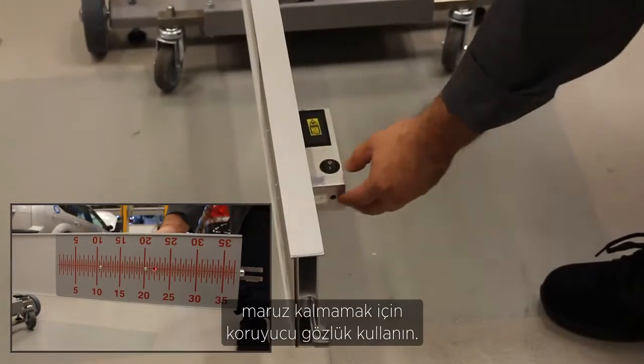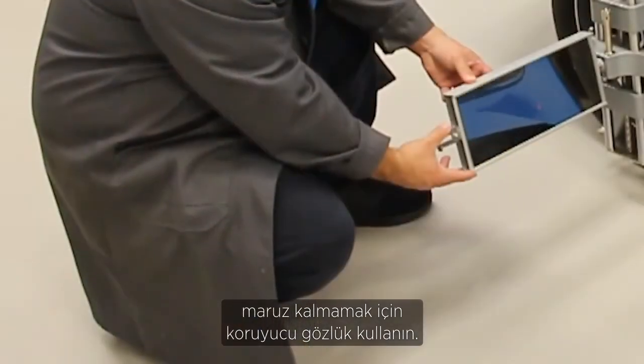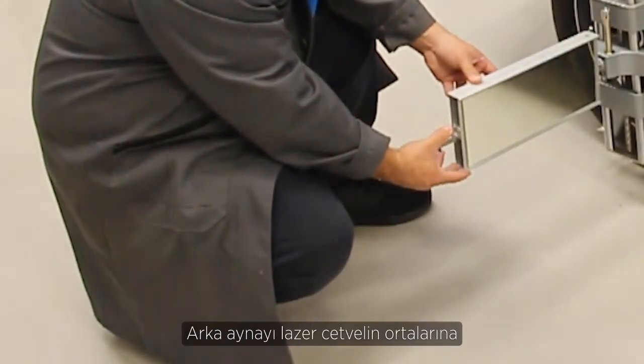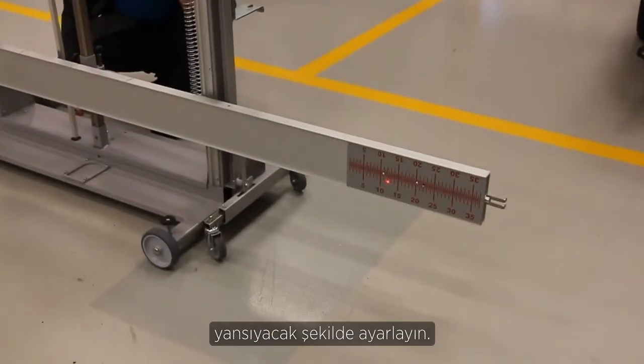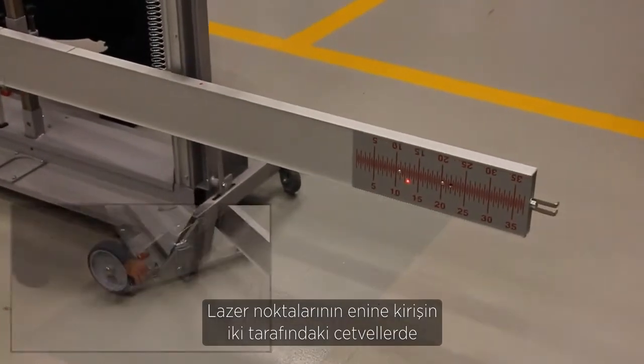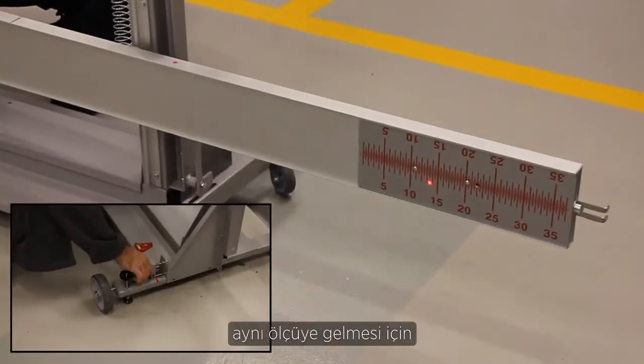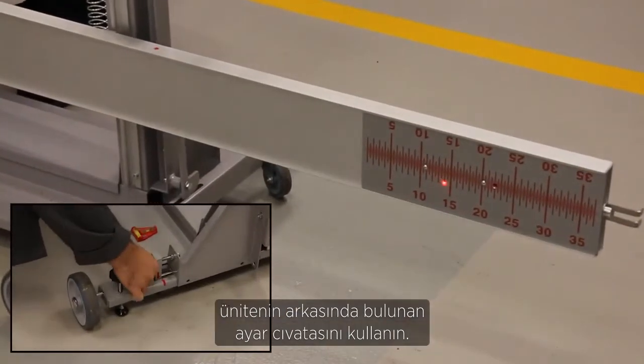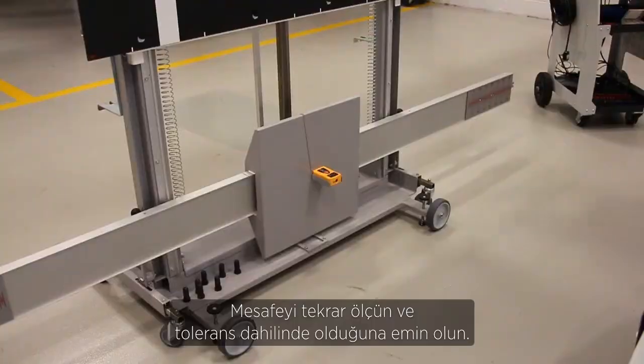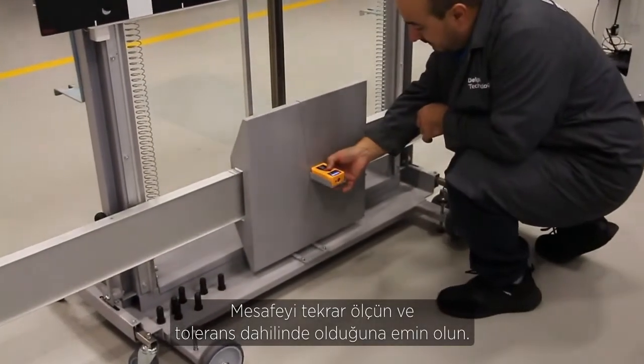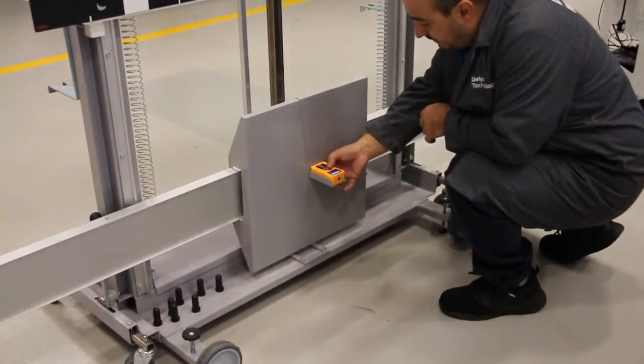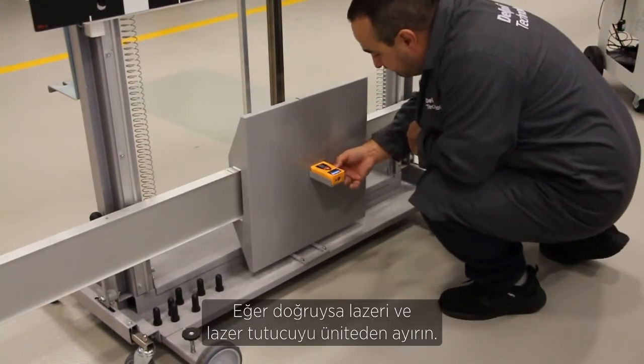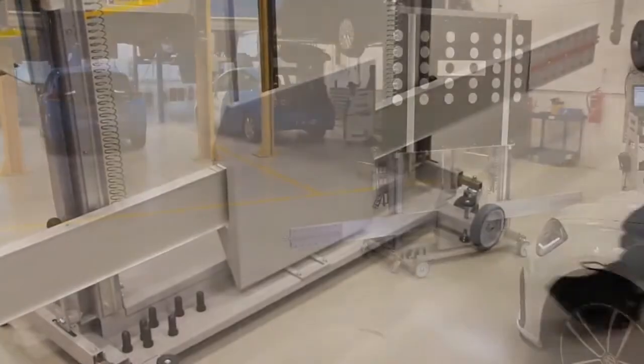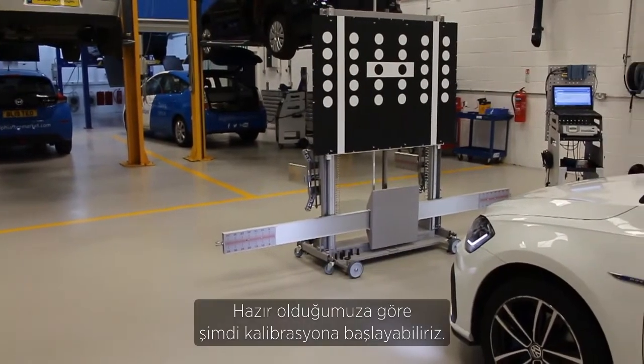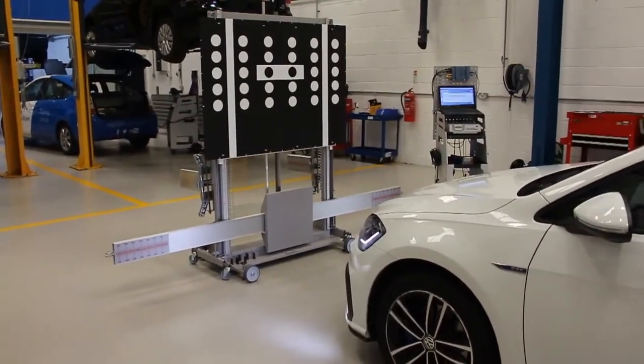Switch on the two lasers at the ends of the crossbeams, ensuring to wear safety glasses which protect from laser exposure. Angle the rear mirror so the laser is reflected back to the crossbeams and is towards the middle of the scale. Using the adjustment screw on the rear of the unit, adjust until the laser dot is equal on both the left and right crossbeam scales. Recheck the distance measurement to ensure it's still within tolerance. If correct, remove the laser and guide holder. Now that's complete, it's time to calibrate.